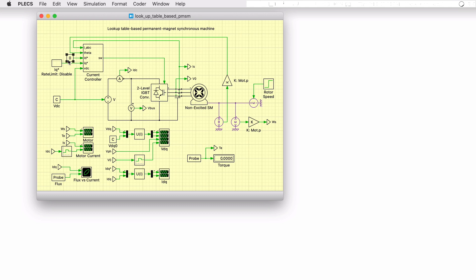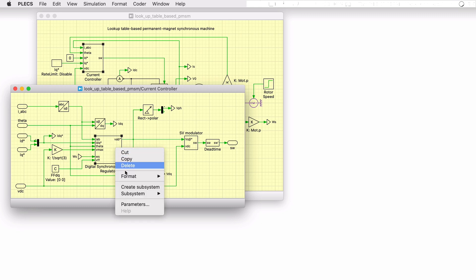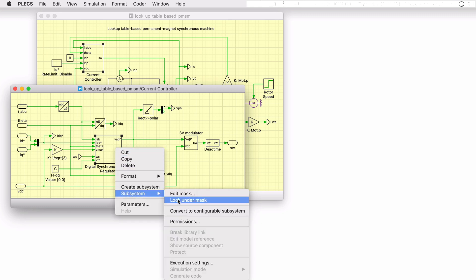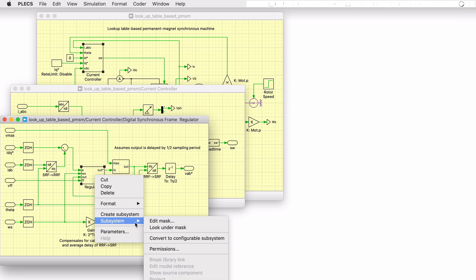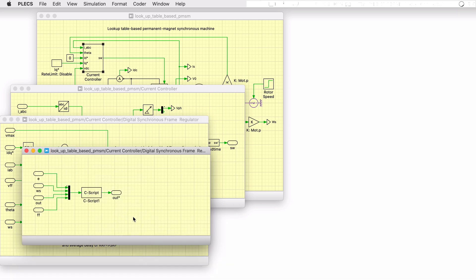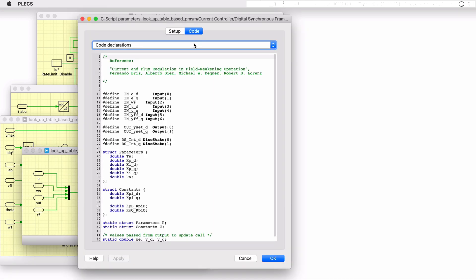Direct and quadrature current set points are provided as inputs to the current controller. The controller implementation is based on a digital synchronous reference frame regulator where there is decoupling based on motor speed. State limiting and anti-wind-up mechanisms are included as well. Proportional integral controllers are implemented for the current regulation in the D and Q axes using a PLECS C-Script block.